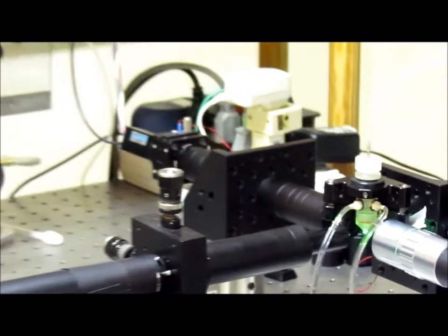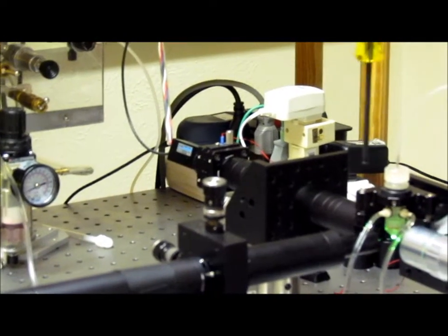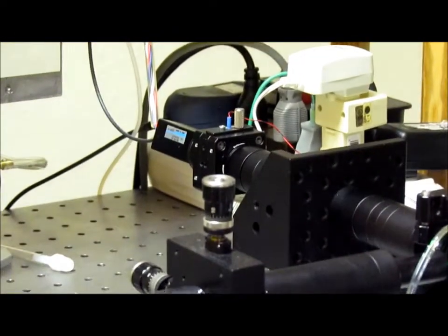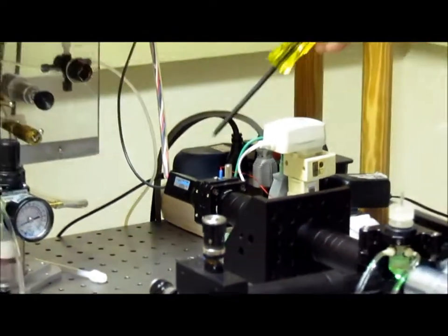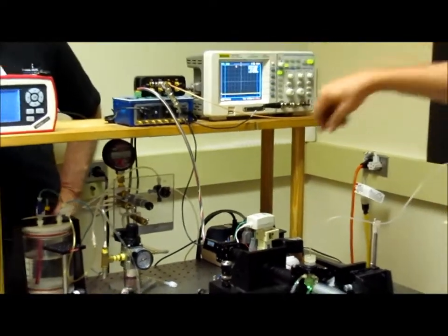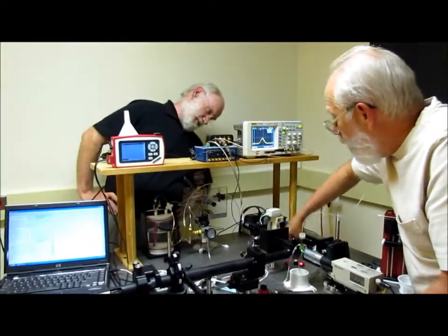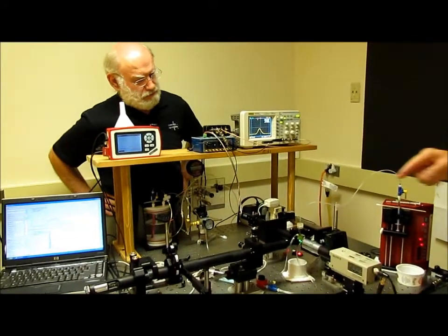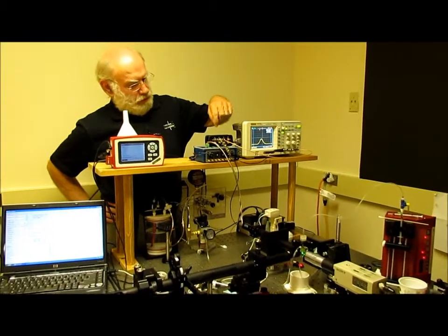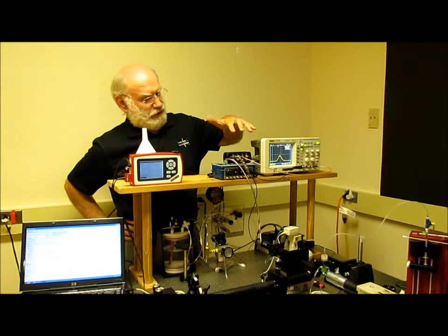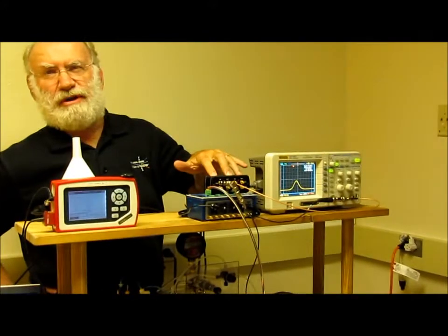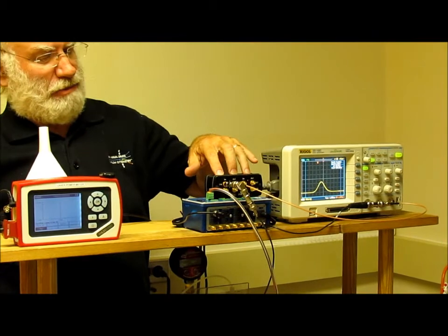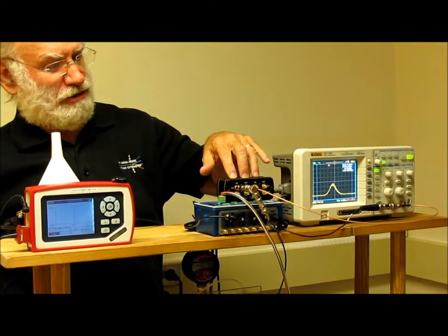The fluorescence from the particles is collected by a lens in the back here and directed through a series of tubes and filters and another lens to focus it onto a photodetector in the back here, which is called a photomultiplier tube.